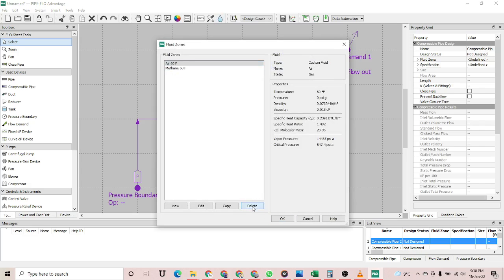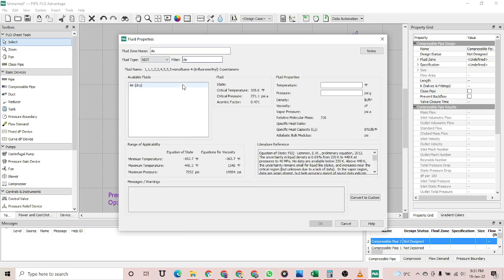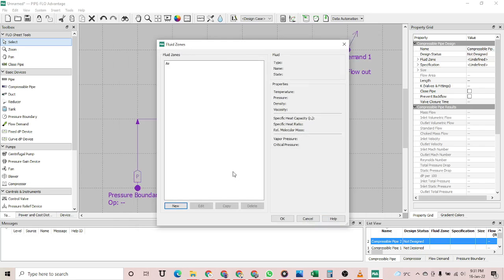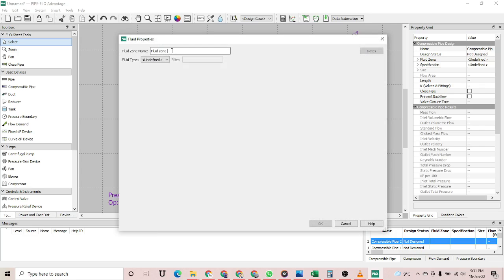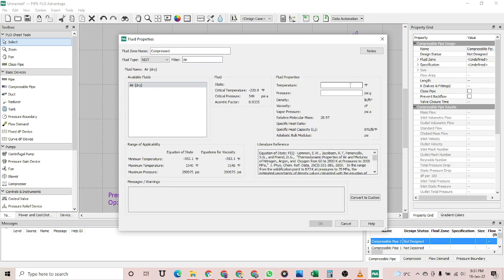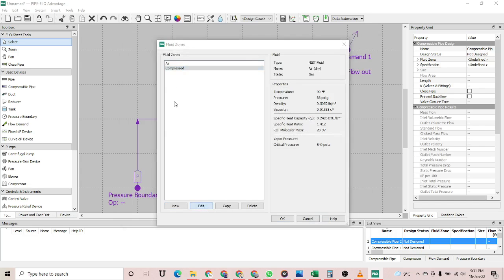There are already built-in fluid zones, but I'm not going to use those. I am going to create a new zone. The first fluid zone will be used before the compressor — air dry, with a temperature of 90 degrees Fahrenheit and a pressure of 40 psig. Then I'll create a new fluid zone called 'Compressed Air', which will be used after the compressor. The temperature remains the same but the pressure will change.